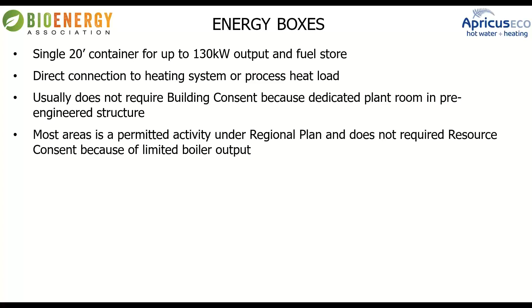Looking at the energy box, we've got 3 models in this region of 20-foot container, from 64 up to 130 kilowatts. There are 2 130 kilowatt versions because we've got different storage capacities depending on the arrangement. With less storage you've got more room in the container for other system components—maybe a heat exchanger or some more system pumps. We're not going to get a buffer in there, though. We could with 64 kilowatts, but nothing more than that.